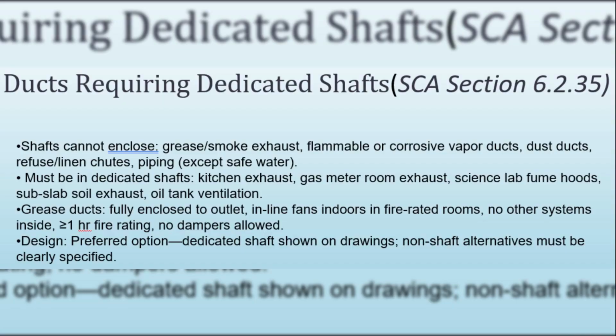When we talk about ducts that require dedicated shafts, the focus is on safety and compliance with NYC mechanical code. First, certain ducts cannot share space with other services. This includes ducts for grease and smoke exhaust from kitchens, ducts for flammable or corrosive vapors, ducts moving dust or stock, and also refuse or linen chutes. Piping is also excluded, except for non-combustible water lines or other safe, non-toxic materials. Because of this, some ducts must always be run in their own dedicated shafts. These include kitchen exhausts, gas meter room exhausts, science lab fume hoods, sub-slab soil exhausts, and oil tank ventilation ducts.